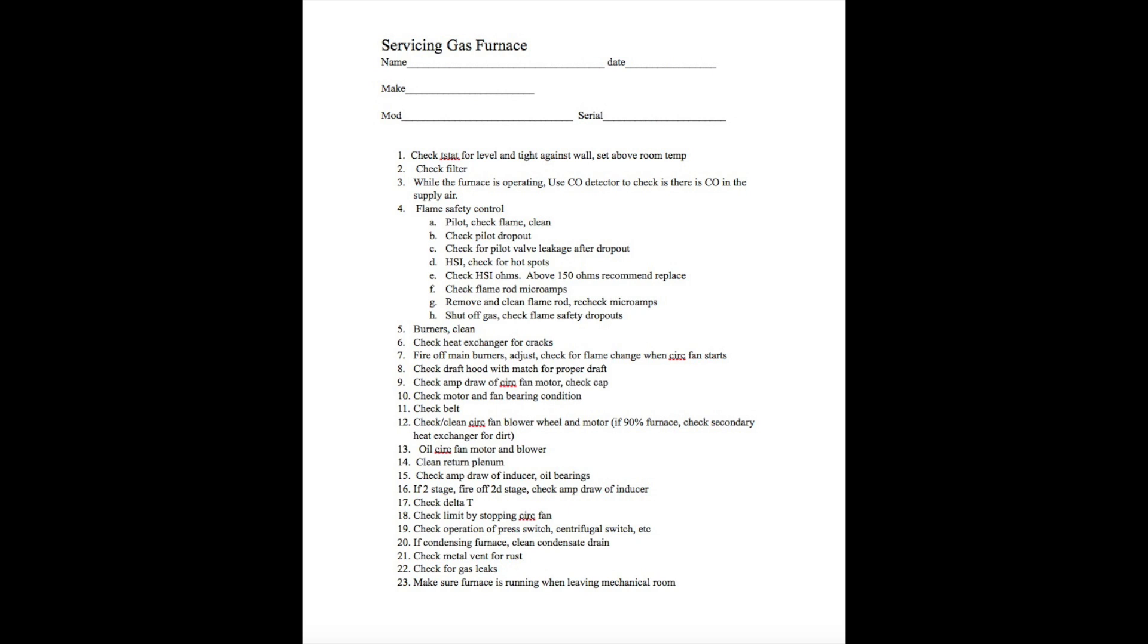If it has a pressure switch or centrifugal switch, you need to check the operation of those switches. Don't disconnect a wire to test them. You got to pull the hose off. There's a hose on those things. Pop that hose off. If the furnace immediately shuts down, then you know it's working properly. Most of these furnaces actually check that themselves. There's a few older ones that didn't, but most of them check themselves. The centrifugal switch is pretty unusual anymore, but it's a switch on the inducer motor that makes when it comes up to speed. It has to be open when the inducer shuts off. So it should be open and then closed when the inducer comes on.